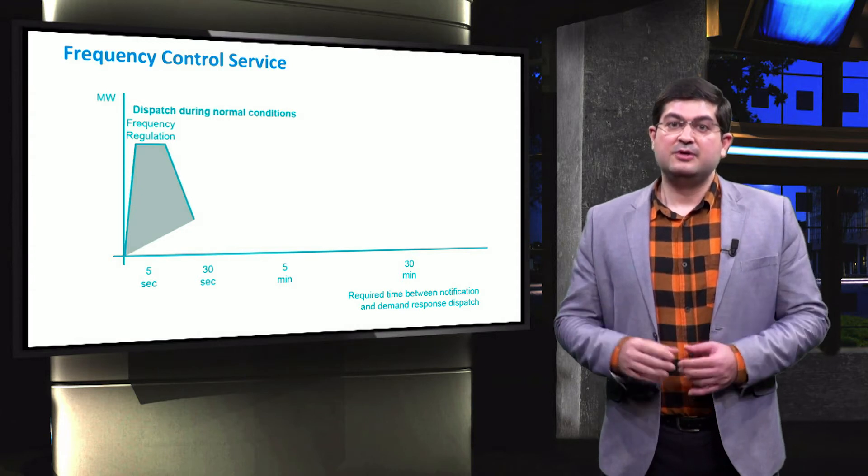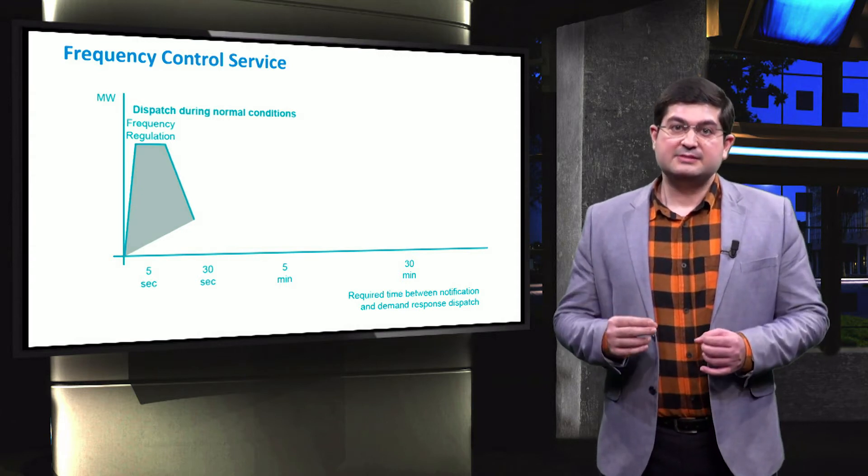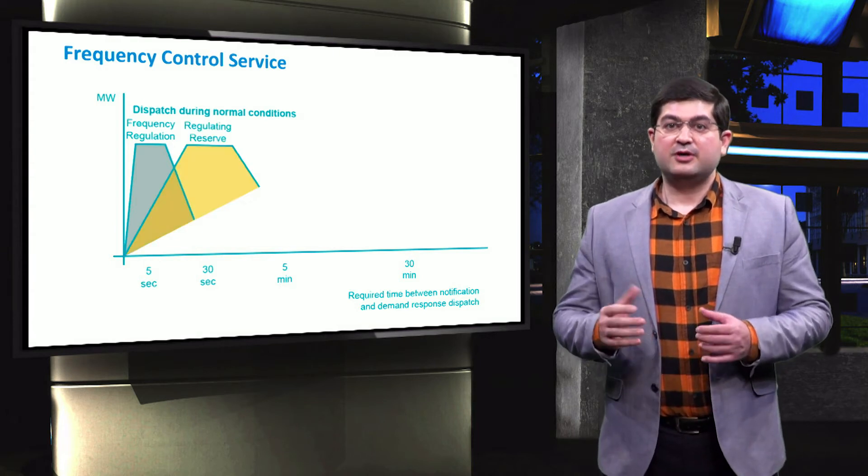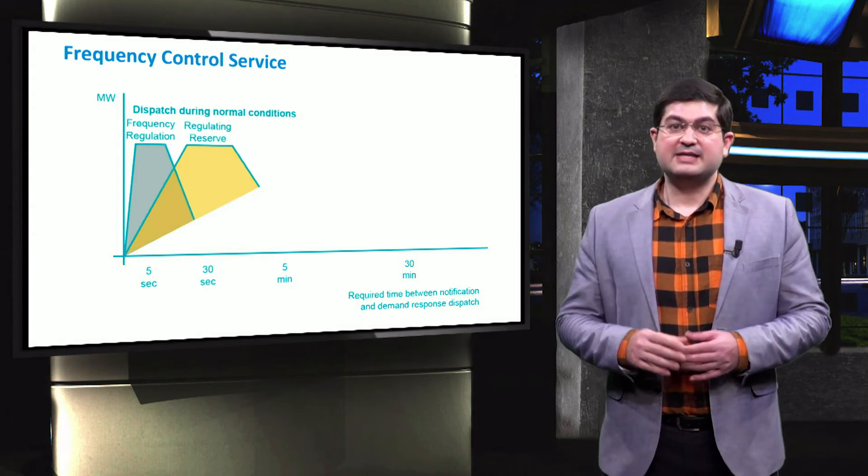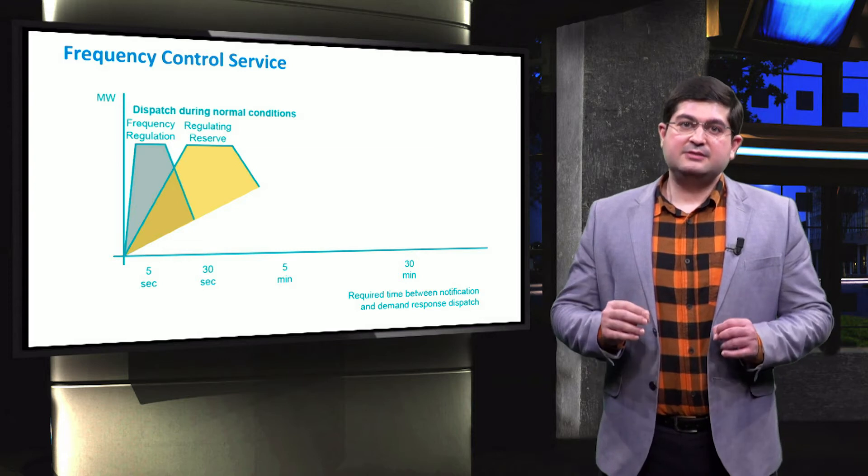The regulating reserve, which is the secondary control, works within several minutes in a centralized manner, while load following or tertiary control is activated manually within several hours.